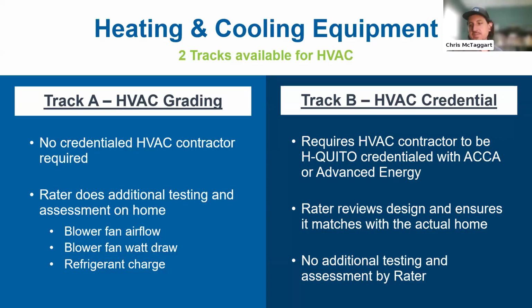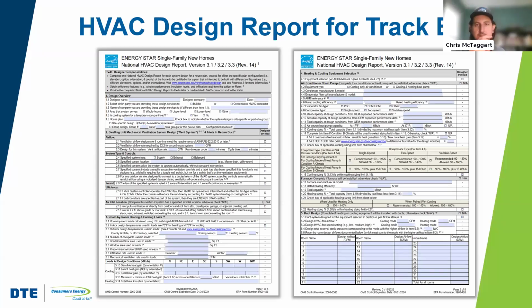And then finally, we have refrigerant charge. Typically, raters are not actually doing physical measurement of refrigerant charge, because generally speaking, raters are not credentialed or licensed to perform direct physical measurements of refrigerant, but there is an indirect, non-destructive method to be able to perform a refrigerant assessment that's based off of temperature considerations of the system. Or alternatively, the rater can get a photographic documentation of a weigh-in method by the installing contractor to document that process of refrigerant charge verification. Okay, so that kind of gives you the broad overview of the options for getting in the door. You could either work with your rater, who is an HVAC grading trained and certified rater, or you could have a credentialed contractor through an H-QUITO program, who is the installing contractor.